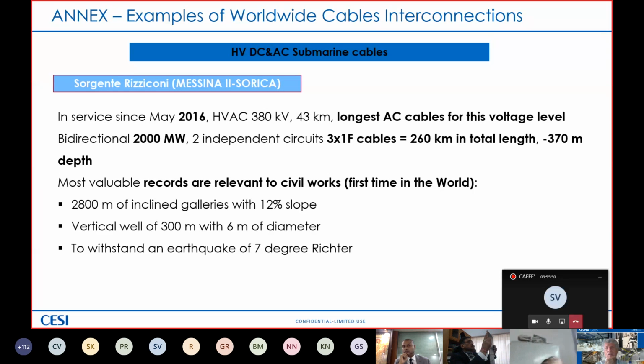This is Messina 2. This is AC. This has been in service since 2016. It's only 43 kilometers, a 380 kV interconnection, but it's three-phase, so in total it is a 260 kilometer connection. The depth is much less, 370 meters, but there are some records also for these AC submarine cables. It used 2,800 meters of inclined galleries with a slope of 12% to take care of the different layout situation. It has a vertical well of 300 meters with 6 meters of diameter. So you can imagine how you can feel on top, looking at the downhill.